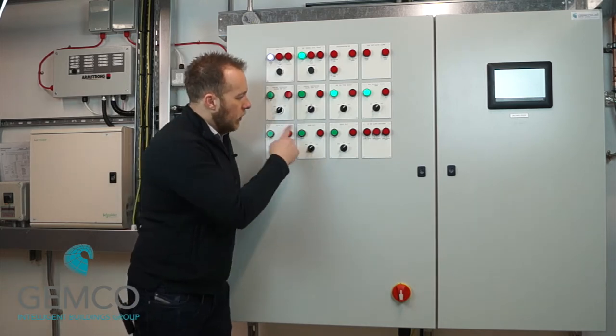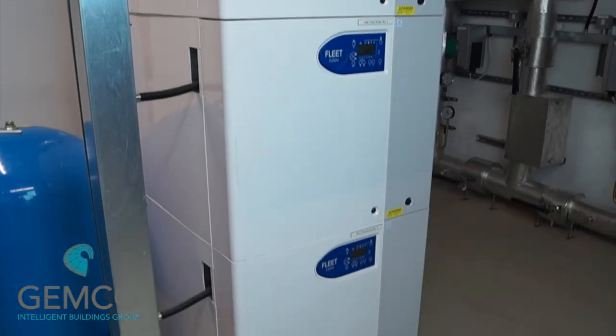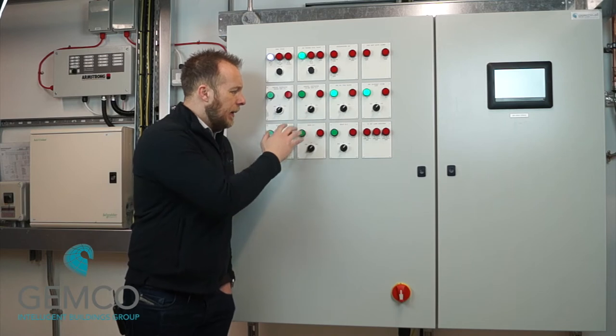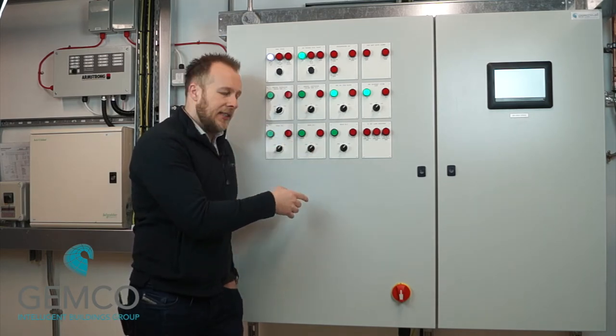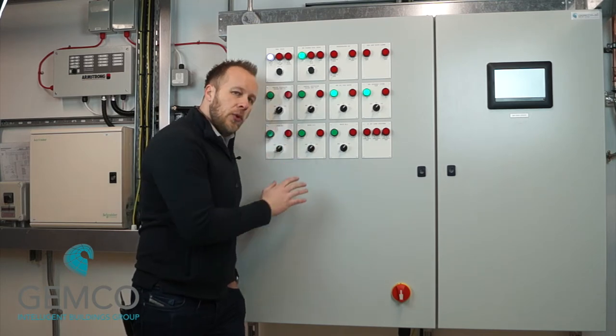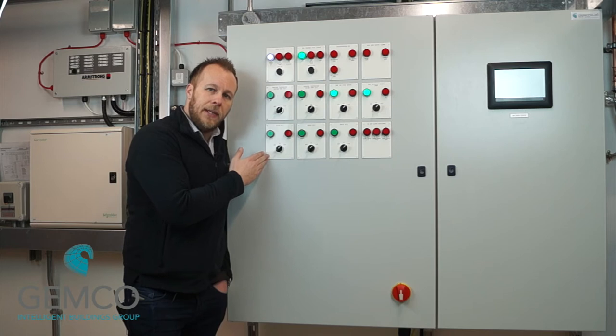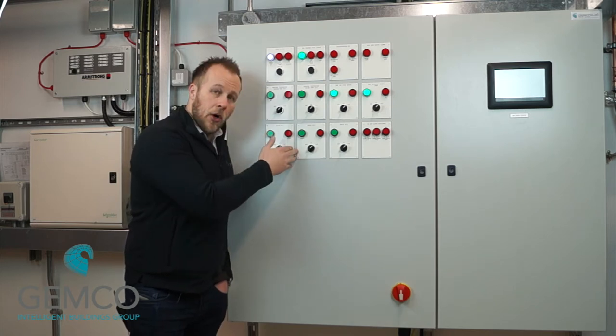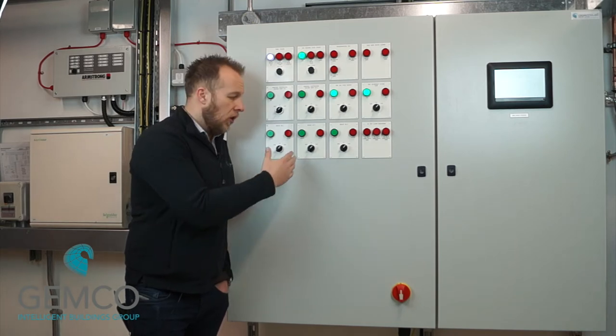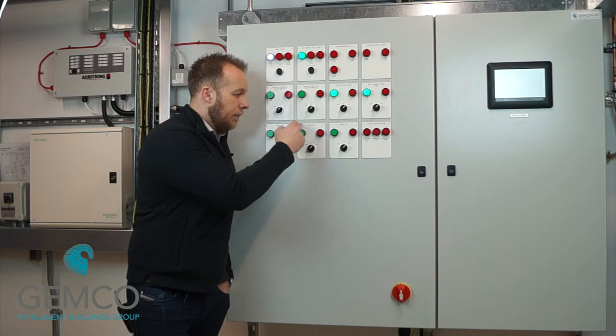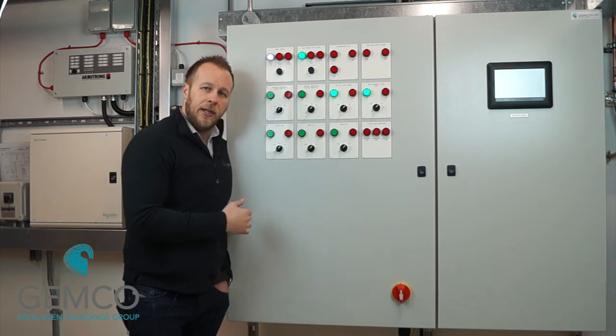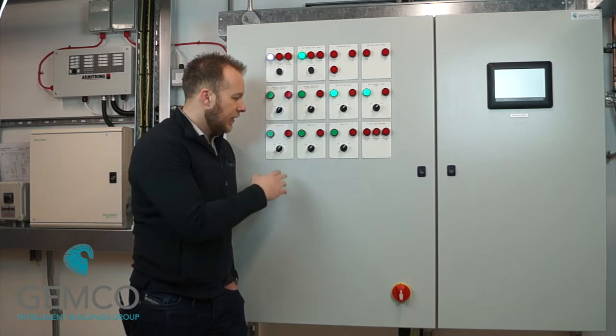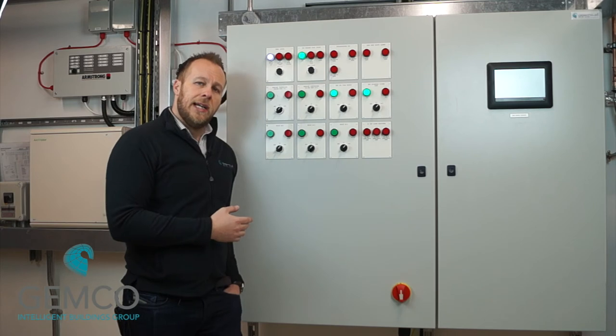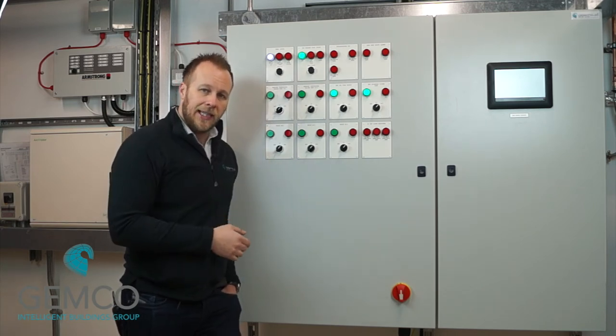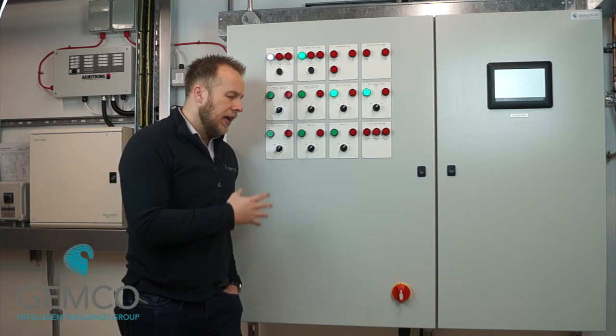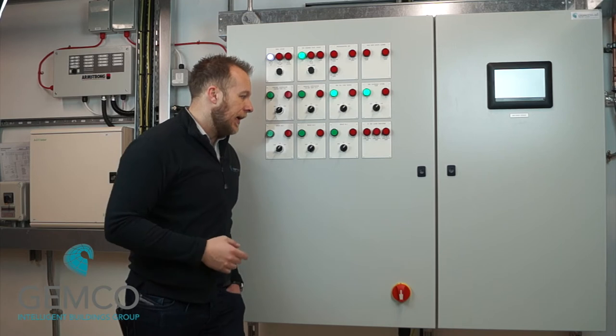So moving on to the boilers, just like the pumps, there's three modules there, the three boiler modules. Just like the pumps, the duty is rotated on a weekly basis. The only difference is the boilers load share as well. So although Monday morning boiler one may be the lead, we see boiler one come on, and if the demand is too great for one boiler module to cope with, then it may bring on boiler two to help top up the temperature to the set point of 70 degree return. Okay, so we work to the return on those because it's a far more efficient way of controlling the boilers. The boilers are sequenced in order to maintain return temperature of 70 degrees. Again, that's adjustable via the head end or the display, which we'll go through in just a minute.